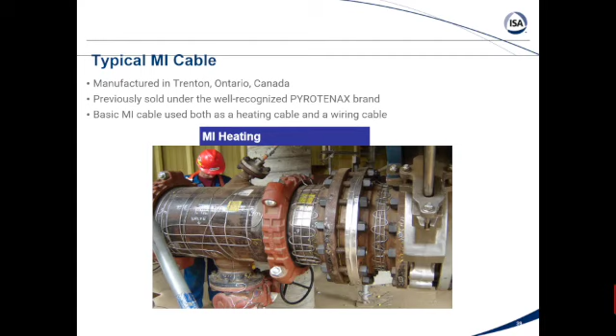So when you get into power plants, for example, your HP drum lines, you have some really high temperatures involved. And then some people think, well, if it's so high temperature, what do you need it for freeze protection? Sometimes, and a lot of times in these power plants, this heat tracing is only really needed when the plant's shut down and not running. But if you need it, you need it. You can't be cracking pipes all over the place. So an MI cable can do the same thing, freeze protection, but also give you higher exposure temperatures and still without breaking down.